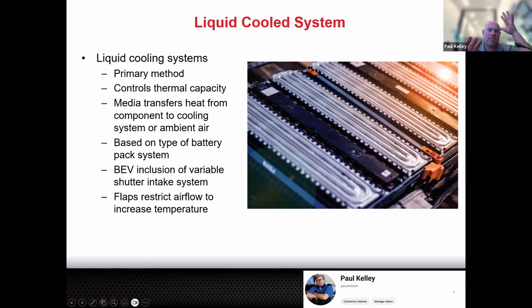Just a rough estimate: comparing air cooled versus liquid cooled, liquid can often move four times the heat energy per volume. The easiest example is intercoolers - an air-to-air intercooler of a certain size would be equivalent to a liquid-to-air intercooler a quarter that size. Liquid cooling needs only a quarter of the surface area. Now, we're not going to give it just a quarter of the surface area - we're going to give a bunch, which means it can provide up to four times the heat transfer. Liquid cooling is much more effective at moving big volumes.